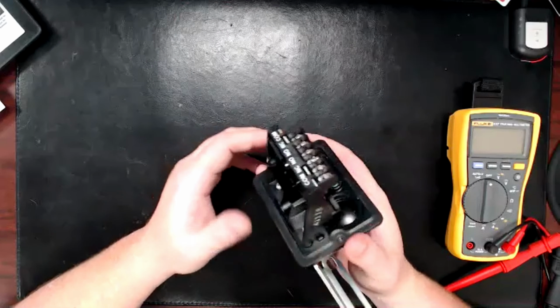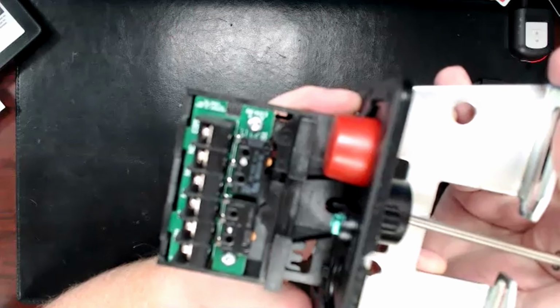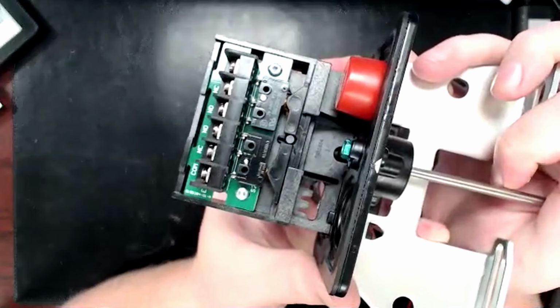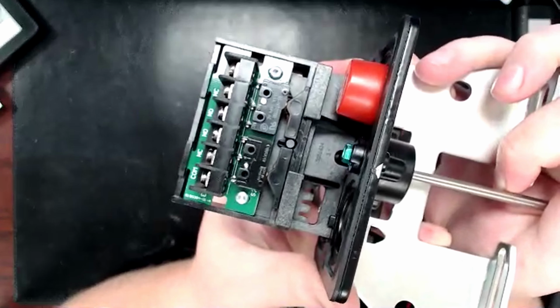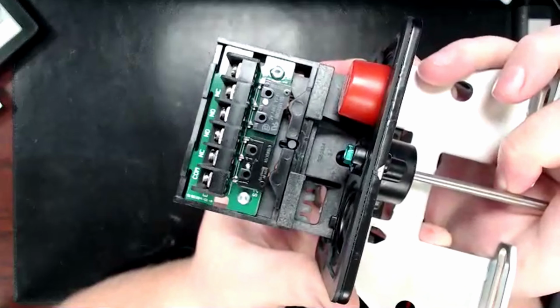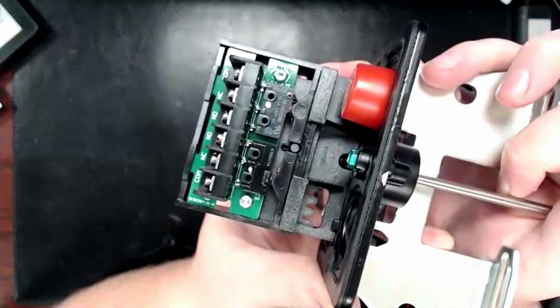And then down here underneath, you see those little orange bits there? Those are actually the switch. As this goes over, it actually pushes the switch up. Let me see if I can get it to sit on it. So you see when it sits right there, it pushes that switch in, and this is how it's supposed to normally be set when the valve is in the open condition, whenever it's open, letting water flow through, the way the valve should always sit. That switch should be pushed up.